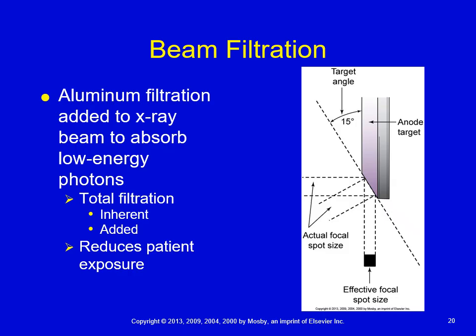All right, in terms of beam filtration, I talked about this a little bit earlier, but just like your coffee filter, there's something bad going on. The something bad is that there are energy levels just above zero up to the max that we set on our control panel for the patient's exam. Some of those X-ray energies being emitted are not even strong enough to exit the patient and help us create the image. Therefore, by law, our tubes have filtration.